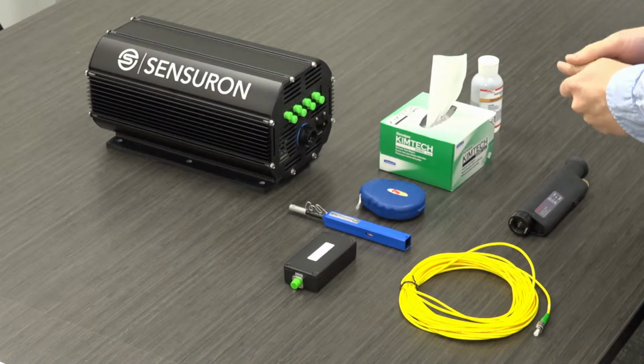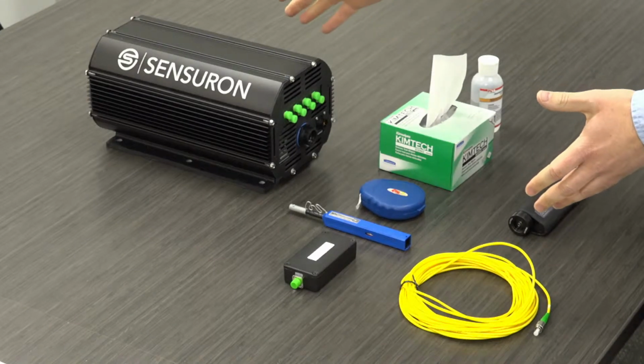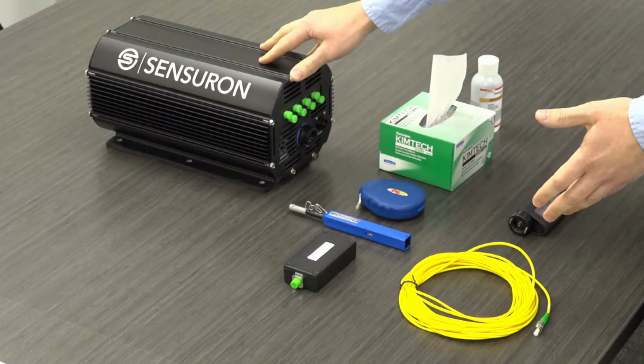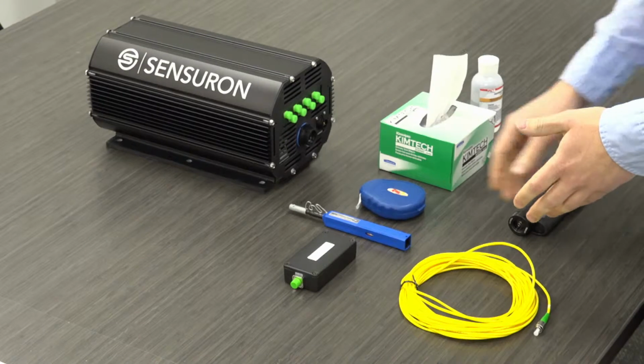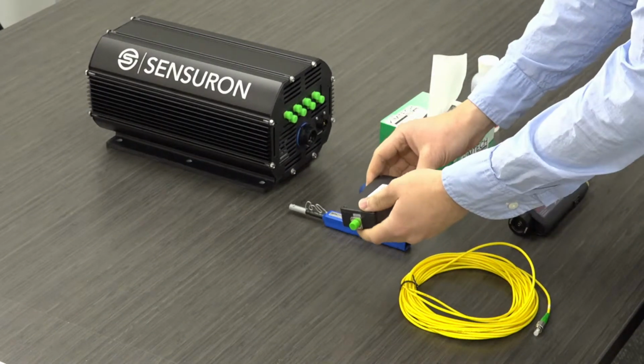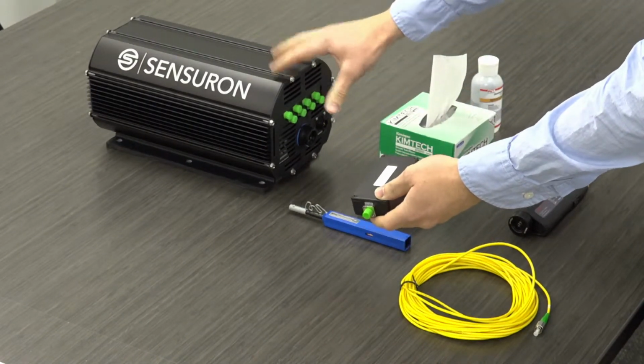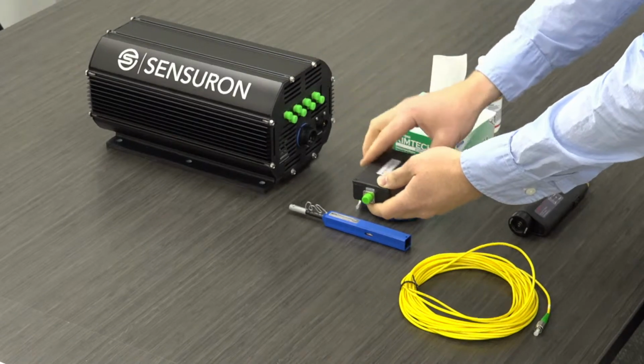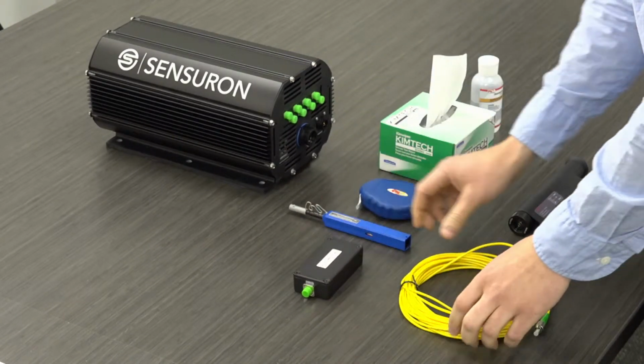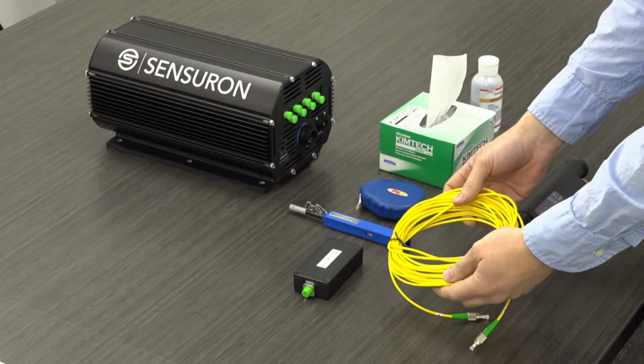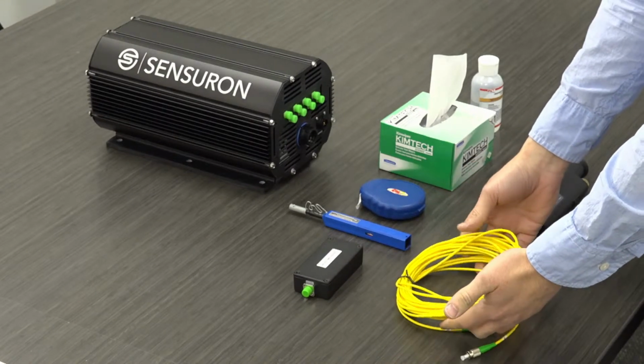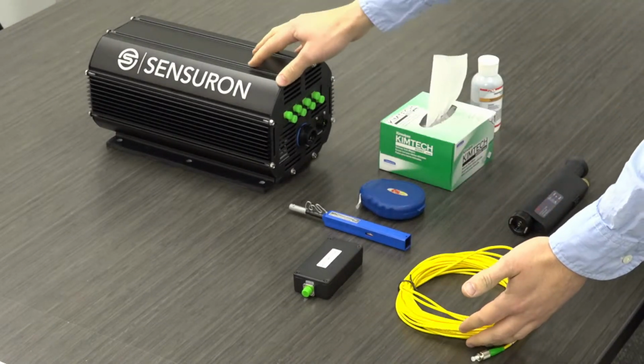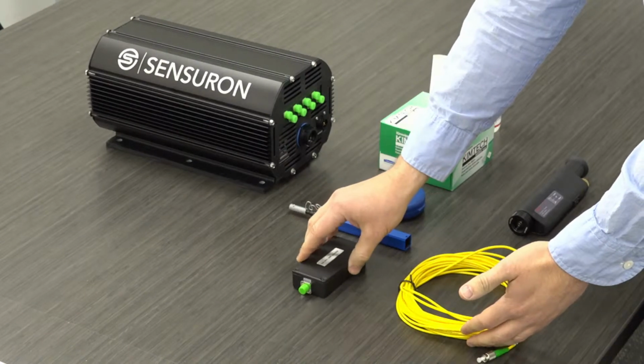So on the components which require cleaning side, we have the RTS 125 Plus sensing system. We have one broadband reflector. This is the unit which has to go one per channel here on the system to define where the sensing length is. And then we also have one FC-APC patch cord. This device serves as the lead cable or standoff length between the system and your broadband reflector.